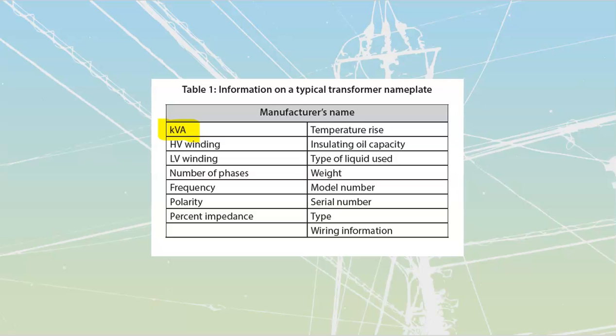If I have a split winding, and sometimes my transformer is going to have split windings, we're going to take a look at those later on, then I'm going to divide the kVA among all the windings of either side. So let's say that this transformer here is 100 kVA, and that the transformer is made up of, and we're going to explain the configuration that we're drawing here later on, but for now we just need to deal with this section. If I've got a transformer that has a high side and a low side that look like this, we refer to this as a multi-coil transformer.